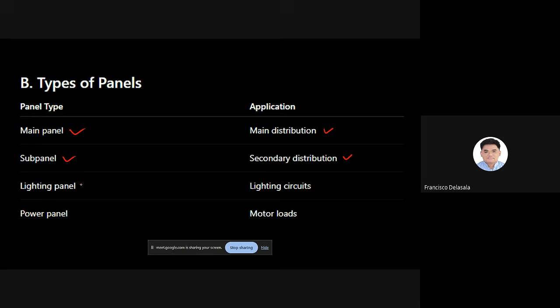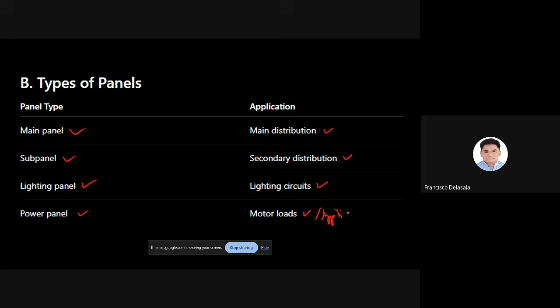Okay, so we have types of panels. The main panel, this is the main distribution. Kapag may isa tayong building, we have the main panel in which we could see the main breaker of the whole building. The sub-panel is a secondary distribution, usually ito yung nakikita natin per floor, tinatawag na DP, distribution panel. They have the lighting panel, this is for lighting circuits. And the power panel is for the motor loads or the appliance circuit. So yan po yung iba't ibang klase ng panel na makikita natin.